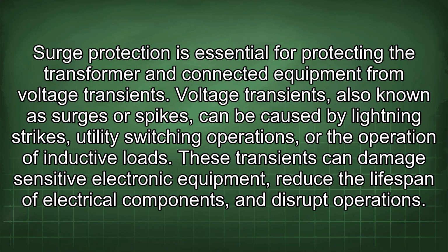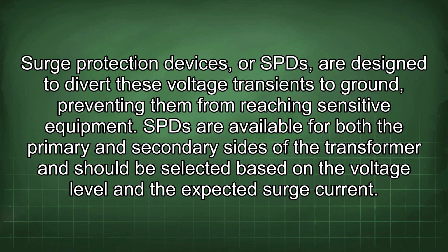Surge protection is essential for protecting the transformer and connected equipment from voltage transients. Voltage transients, also known as surges or spikes, can be caused by lightning strikes, utility switching operations, or the operation of inductive loads. These transients can damage sensitive electronic equipment, reduce the lifespan of electrical components, and disrupt operations. Surge protection devices, or SPDs, are designed to divert these voltage transients to ground, preventing them from reaching sensitive equipment. SPDs are available for both the primary and secondary sides of the transformer and should be selected based on the voltage level and the expected surge current.